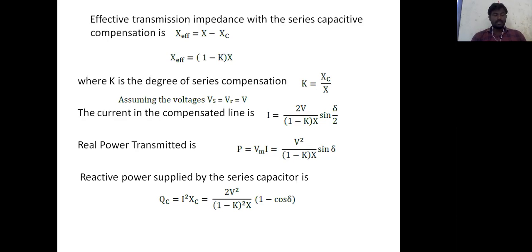The extent of the effect of compensation depends upon the number of locations and the circuit arrangement of the series capacitor and the shunt reactor stations. From the practical point of view, it is desirable not to exceed a series compensation of 80%. If it is 100% compensated, it would cause series resonance at the fundamental frequency.